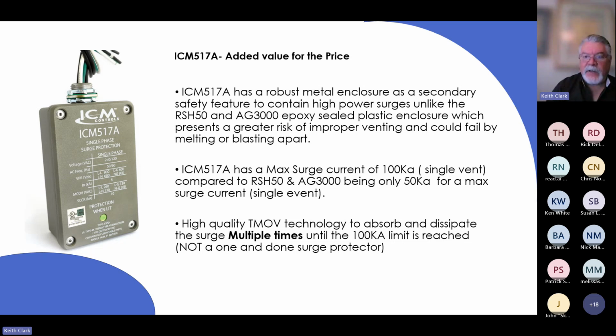And I watched a video that one of our engineers has of one of these things blowing up, one of the plastic devices, and it's like a small bomb. It was shocking to me. I was like, oh my gosh. So it's worth considering where this thing is mounted, and do you want to take the additional risk should something catastrophic happen? This thing's in a metal enclosure that is going to be a secondary type of protection, explosion proof type of scenario. So the other ones, the melting or blasting apart of the plastic, which is what I saw, is crazy. This is just a better device all the way around.